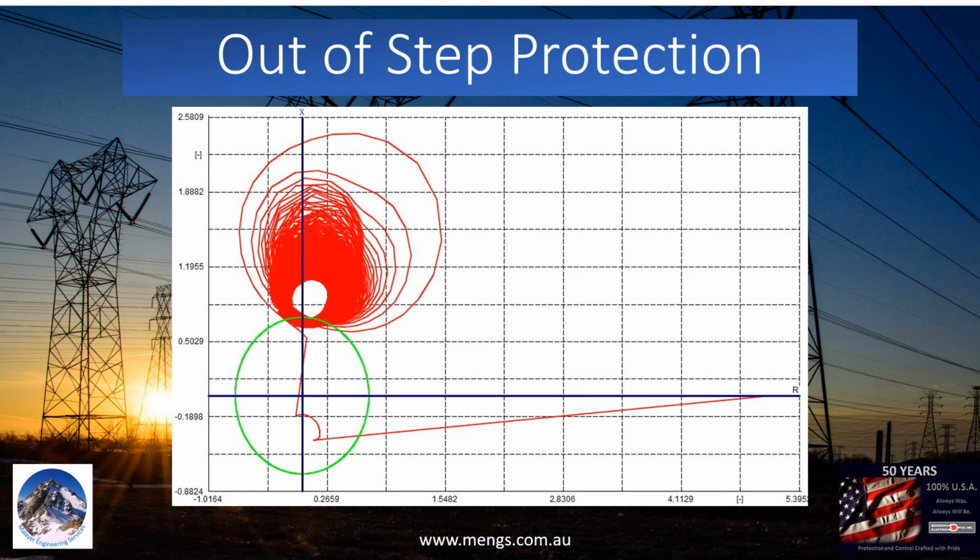As we see, the impedance enters the MHO zone and exits from the other side. In this example we see why using a simple overcurrent for line protection might not be a good idea, as within 400 milliseconds we are not dealing with only a fault on the line but an out-of-step generator as well.